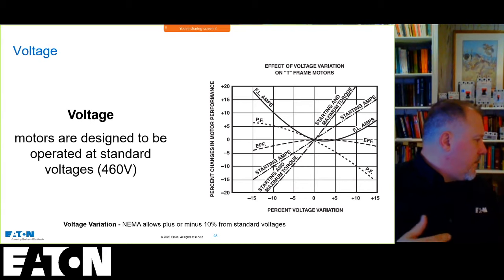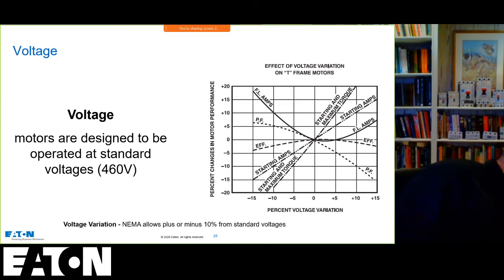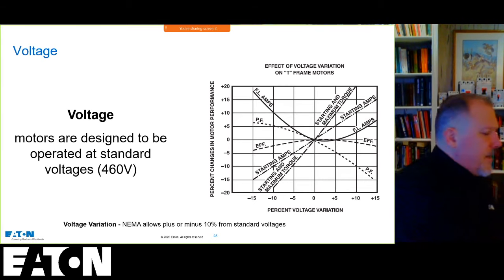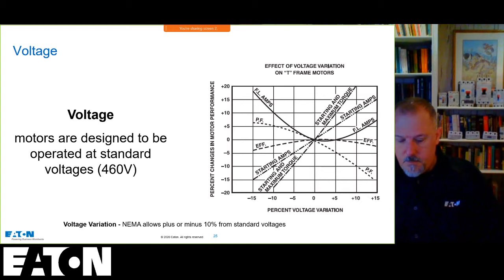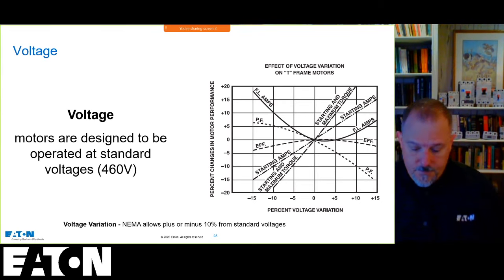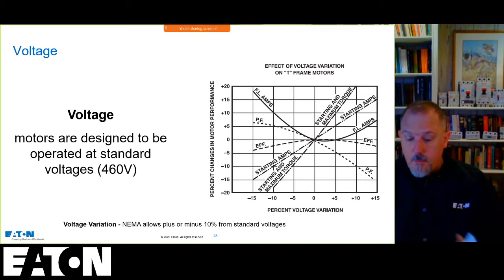just trying to think of some of the other areas. Bear with me here a second. But the temperature that you're running that motor in, the elevation that you're at, all of that impacts the performance of that motor. So I honed in on the voltage, but if you're running something at a lower value, you could impact the temperature rating, which will impact the life of that motor.